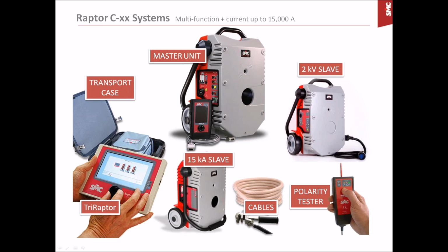Okay, in the template diagram, you can see the schematic drawing of these connections, possibly more clearly than you can see right now. So the first thing I am going to do is to complete the current injection circuit by just closing this terminal, so the circuit goes inside the Raptor and comes out through the protection transformer. So we will get the injection current through this cable here, and we will get the measurements from the secondary here.